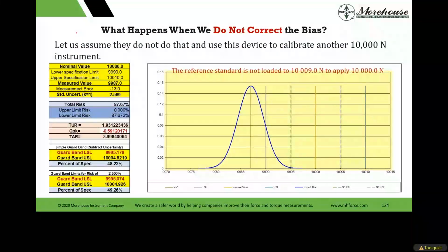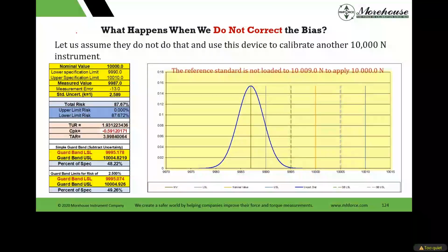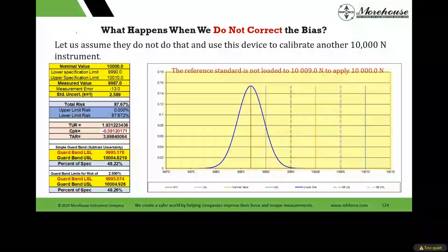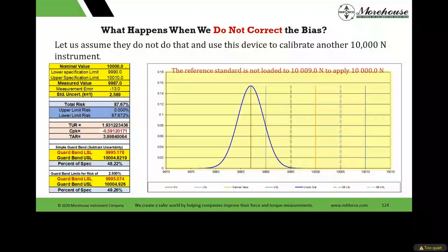So if we look at this, and this is just simple conformity assessment, I'm taking the measurement uncertainty into account. When we look at this and we do not correct for that bias, and all of a sudden I say, I have this device, Morehouse sold it to me, the nonlinearity spec is O2, I paid them for calibration, my data shows O2, I program these two of the points that I randomly pick into my meter, we're at 10,000, I have this offset of 9, and then I go use this device to calibrate something else that they say is good to 0.1%. That's my specification here, 10,000, which is plus or minus 0.1 of 10,000, which means my lower specification limit is 9,990, and my upper specification limit is 10,010, so plus or minus 10.